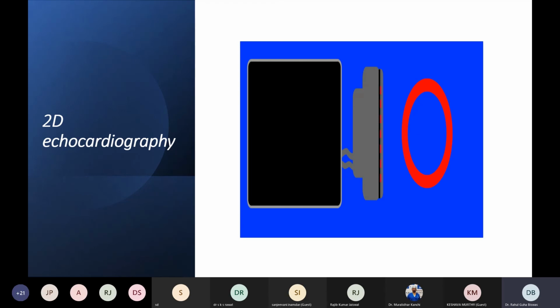It is coming back reflected into the ultrasound. 2D is an amazingly useful application because it will map a particular area of the tissue on your ultrasound screen as a dot, exactly based on the time it takes to come back from the tissue, and the brightness of the dot will depend on the energy with which the sound wave has come back. For example, if the sound has not been reflected, if it has passed on, for example through air, you will get basically no reflection there. It will be dark. And if you have a nice specular reflector, like a mirror, you will get a bright dot coming from that area, and you will identify it as tissue or bone or fat, that kind of thing.